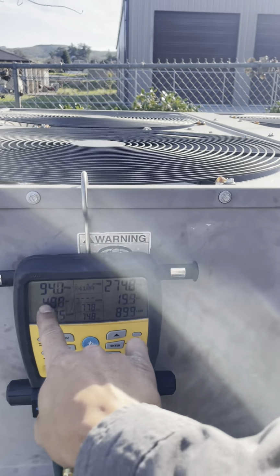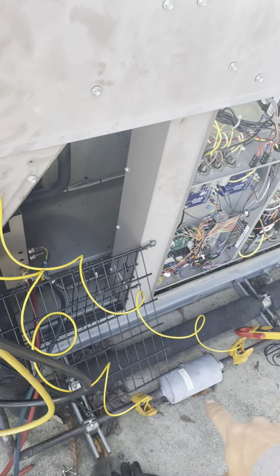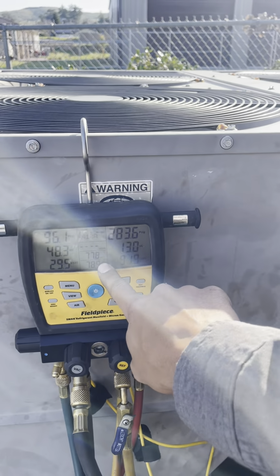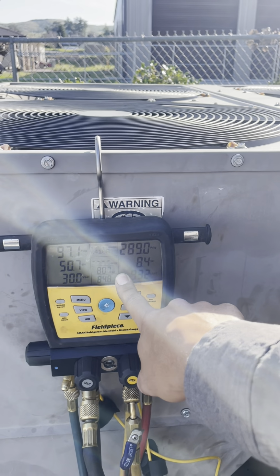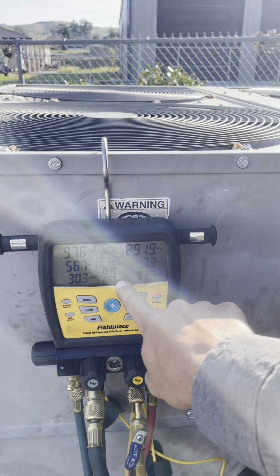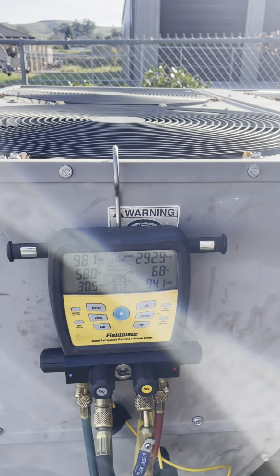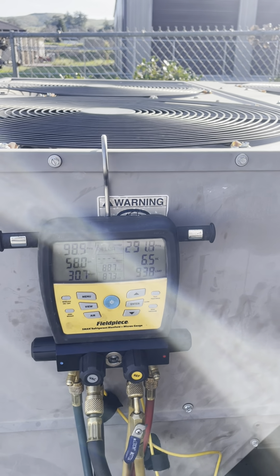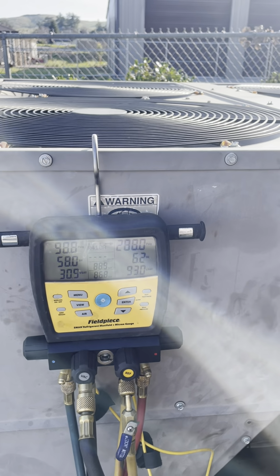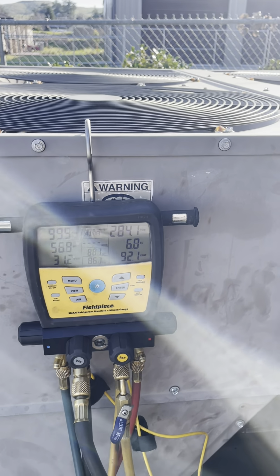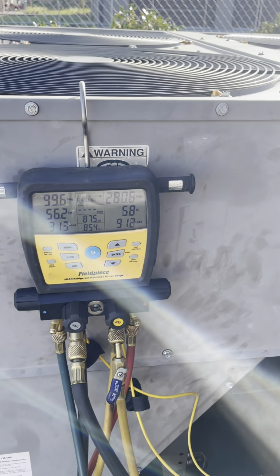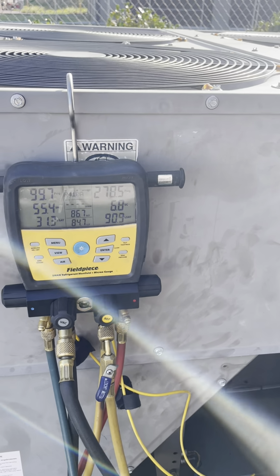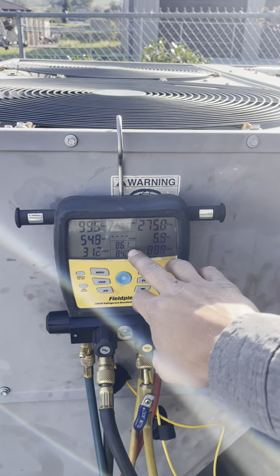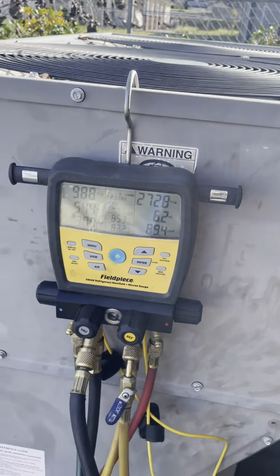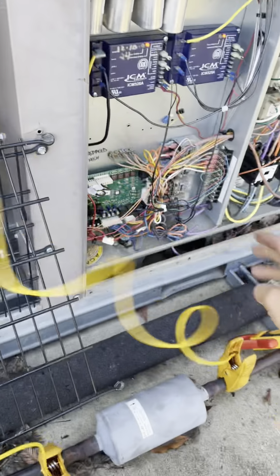The superheat is not accurate because I have both probes on the liquid line right there. But I was just trying to see my temperature drop across my dryer. It's kind of hard to tell. But I would say with these fans running on and off like that, it doesn't really help me out. I might want to run them across the line to make sure that it is actually getting consistent pressure feed to the dryer, so I can measure the temperature differential across it more accurately. But I would say perhaps maybe it's restricted. So I'm gonna take my suction probe back off of here, put it on my compressor.